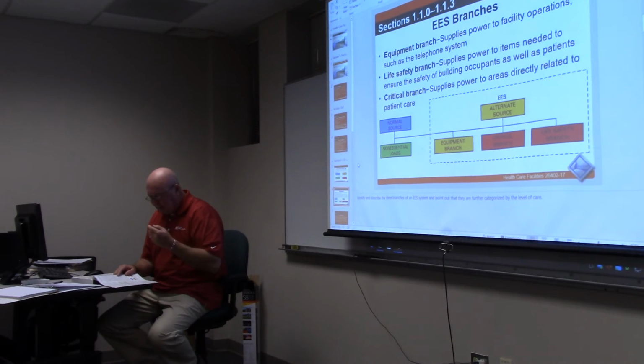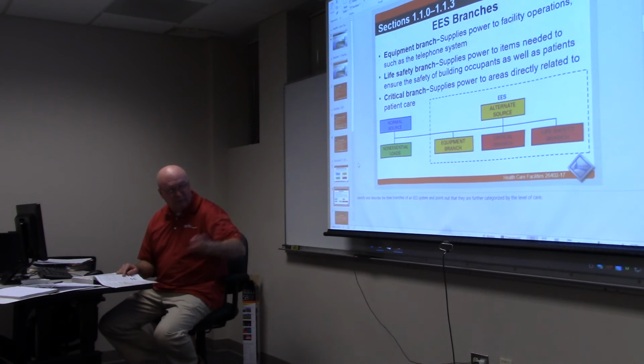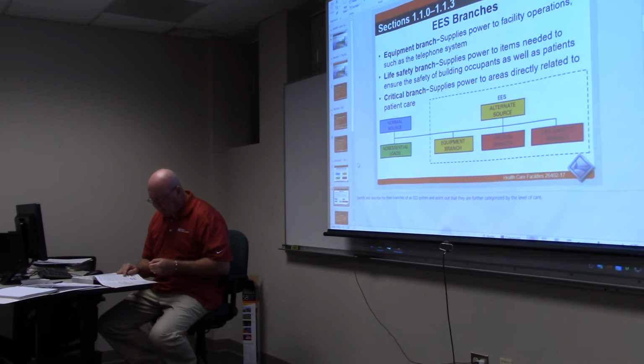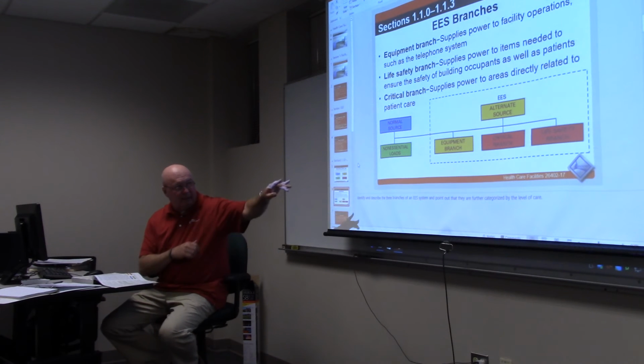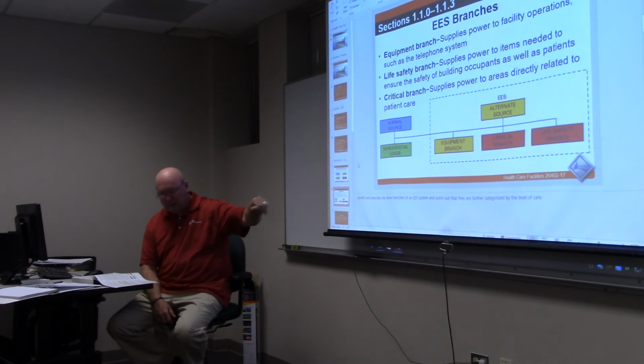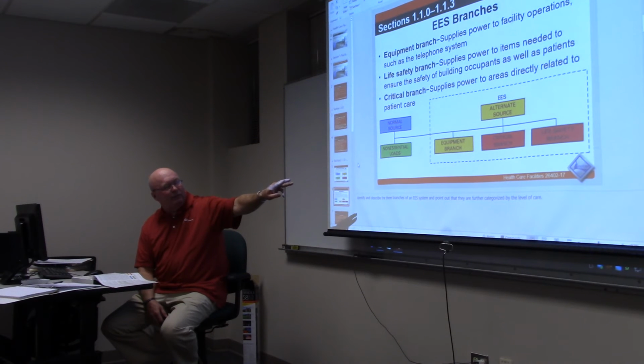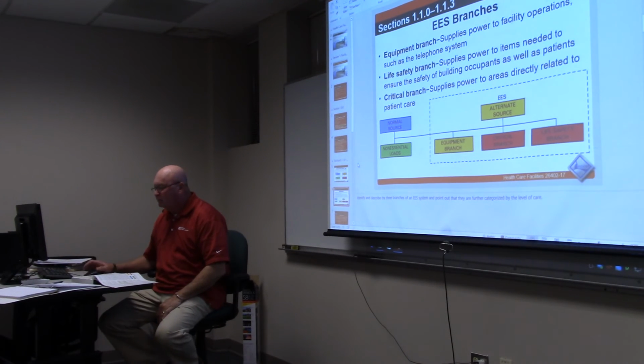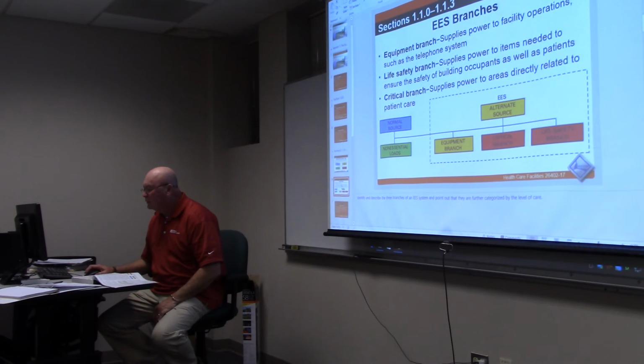The life safety and critical branch consists of those items essential to patient care. The life safety branch ensures the safety of the buildings: exit signs, stairway lighting, alarm system, communication system. The critical branch supplies areas directly related to the patient, including pharmacies, emergency rooms, intensive care units, and so on. So that's the 3 categories: critical branch, life safety branch, and equipment branch. Everybody understand that?